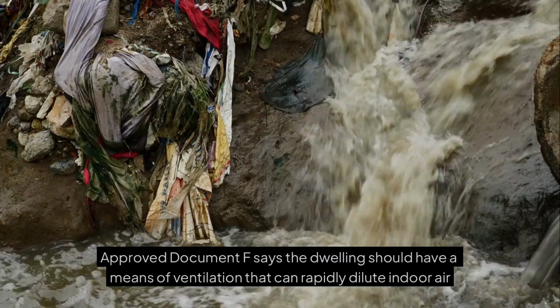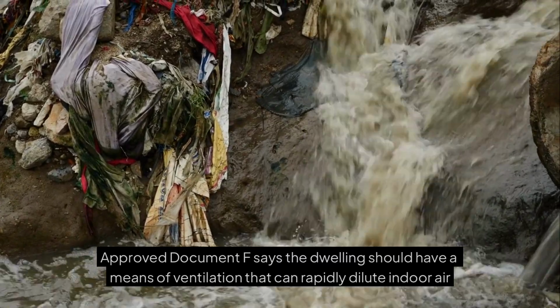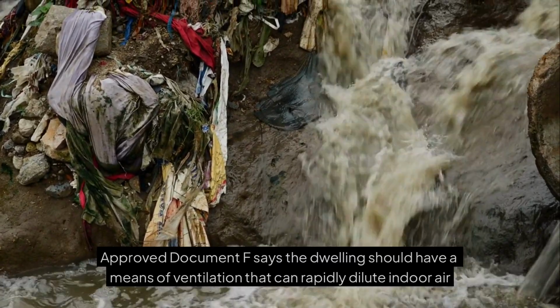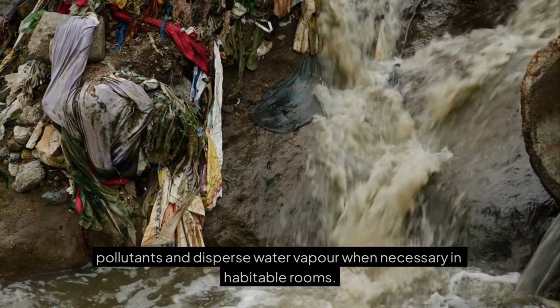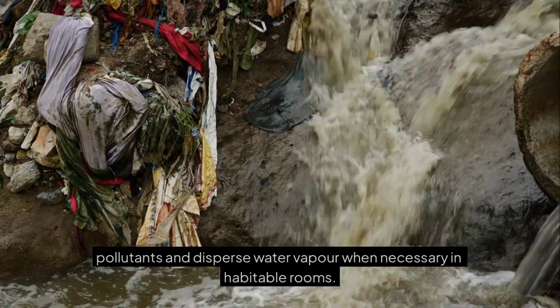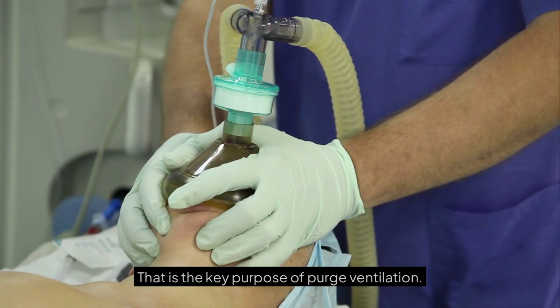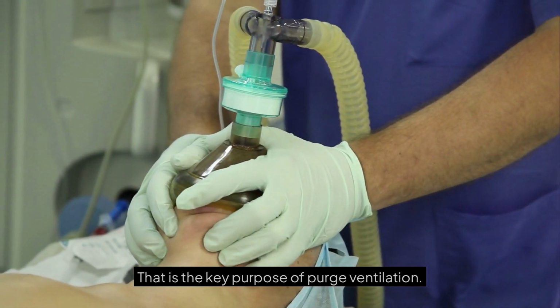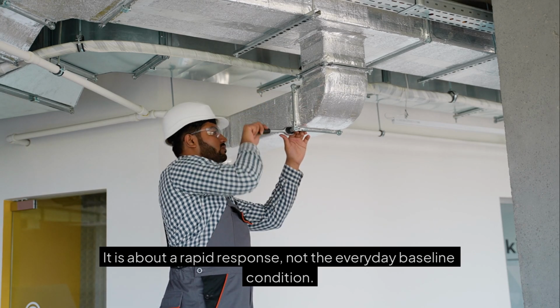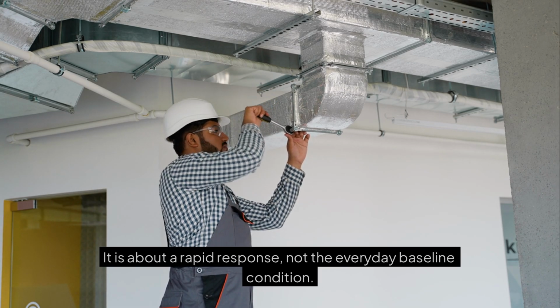Approved Document F says the dwelling should have a means of ventilation that can rapidly dilute indoor air pollutants and disperse water vapor when necessary in habitable rooms. That is the key purpose of purge ventilation. It is about a rapid response, not the everyday baseline condition.